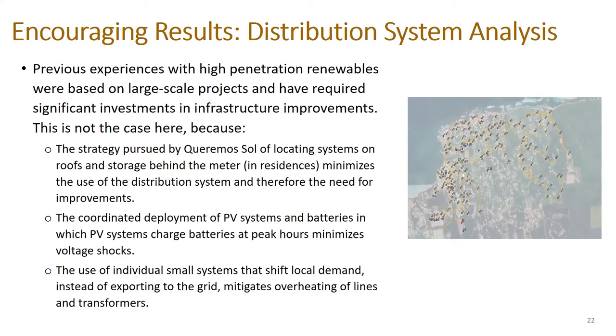When you're at that low load, high PV scenario, you can use the PV system to charge the batteries, just as Derek's graphs generally showed. You can use those PV systems to offset the high voltage that is typically associated with high penetrations of PV systems. By charging the batteries, you mitigate some of those voltage issues just by the very nature of your installation.